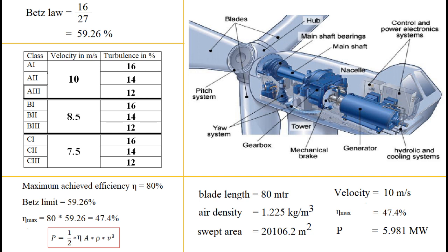Another efficiency-improving and speed control feature is to change the pitch angle. Pitch angle is the angle the blade makes with the swept plane of the turbine. This angle decides how much energy should be converted and how much should be left unused. Sometimes the velocity of wind is too high, so to keep the reaction of wind on the turbine below a specified limit, some energy has to be left non-converted. One more use of this pitch angle is to keep the rotor speed within a specified limit. Both the yaw system and the pitch of the blade are shown on the slide.